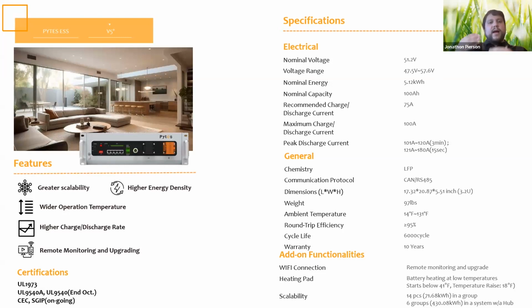We just talked about how if you can decrease that depth of discharge number to 80% or less, that'll increase the longevity of the battery. But at 6,000 cycles, if this battery bank is discharged every day, that's about 17 years of life expectancy. For context, compare that to NMC lithium, or nickel manganese cobalt lithium, which is more conducive to thermal runaway and cascade failures—it's less safe, of course.